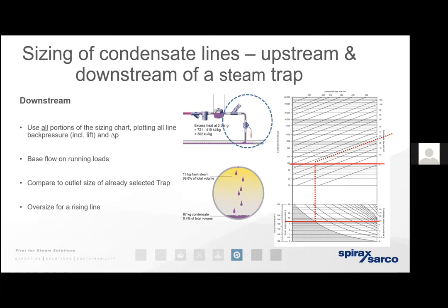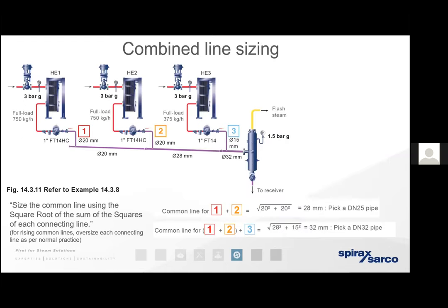The rule of thumb: whenever condensate falls in pressure, it becomes bi-phase. Failing to allow for that expansion is likely to create water hammer and place back pressure on the trap, preventing condensate from passing and encouraging it to back up and flood the process. There's no reason why multiple processes downstream of the trap cannot feed into one common group condensate return line — we just need to ensure the mass flow rate and volumetric flow of flash steam steps up in accordance with each individual process converging onto that group line.